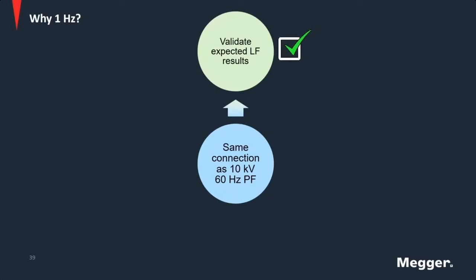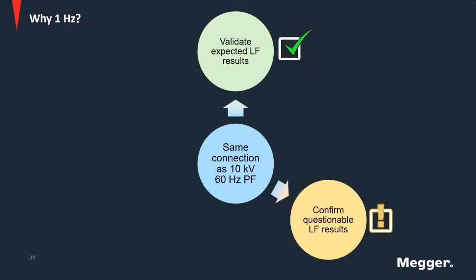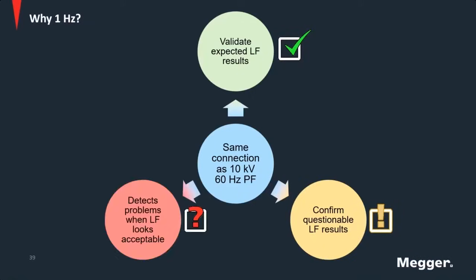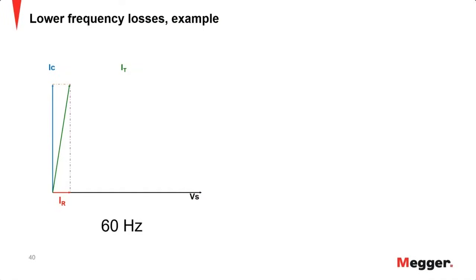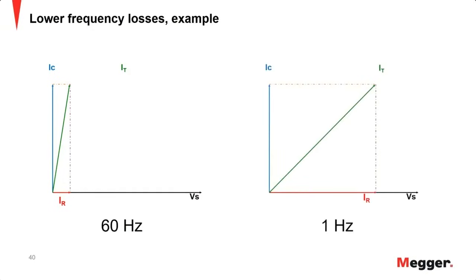Also, when your 60 Hertz results are changing, maybe they're a little bit lower or higher than you measured last time, 1 Hertz can also be used to confirm these questionable results. And then finally, 1 Hertz can detect problems when line frequency looks acceptable. And why does 1 Hertz work? Well, it works because the resistive current is exaggerated at this lower frequency, so it makes up more of the total current than you would see at 60 Hertz.